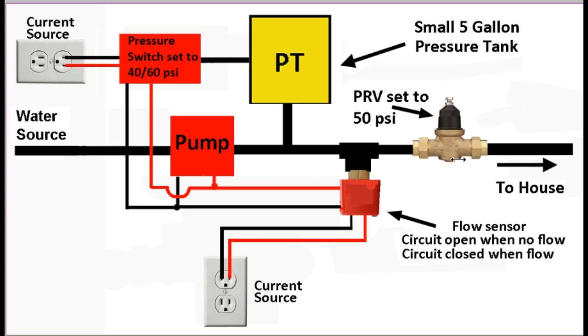So like a cycle stop valve will go on when you wash your hands or flush the toilet, but like a cycle stop valve, it will not cycle during a long run. And you will get constant pressure without the fluctuation at the beginning, and it will fill up this little tank quickly because it's not using the dribble rate. So it's better, and it's cheaper than a cycle stop valve.